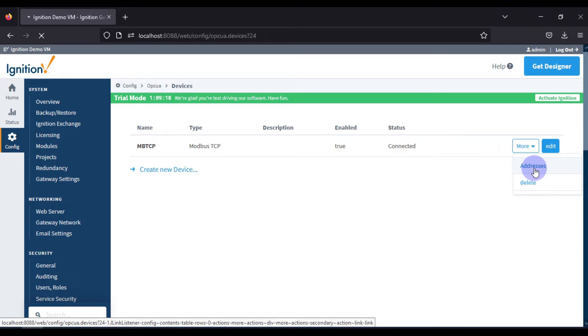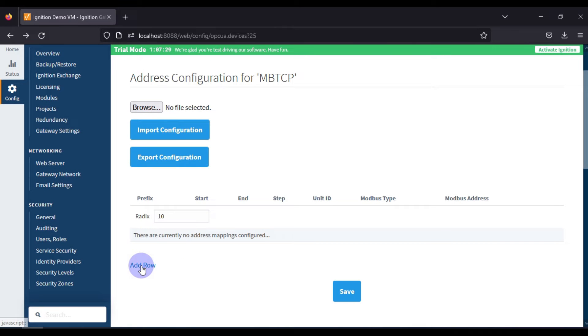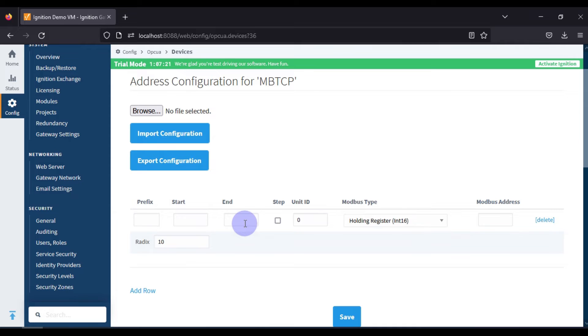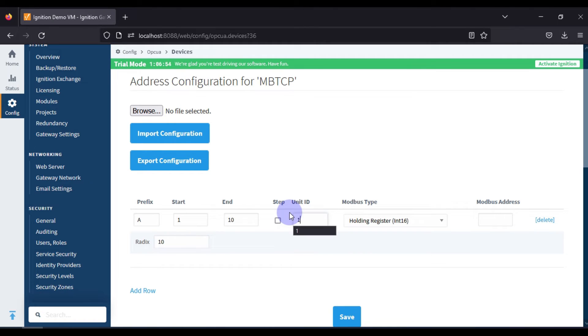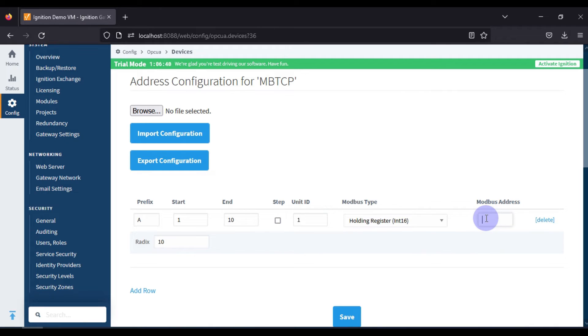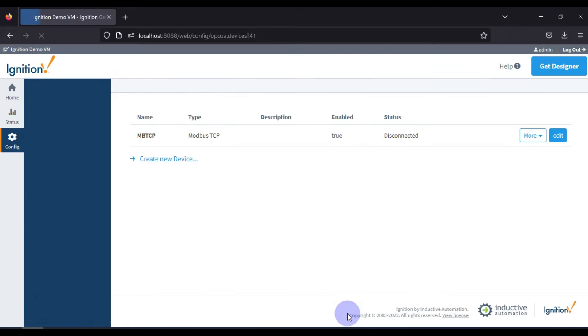Let's go back to Device Connection, open our Modbus TCP device, click More, then Addresses, and click 'Add Row'. We fill in the fields: prefix is 'A', starting address is 1, ending address is 10 — meaning we read 10 registers. The unit ID of the Modbus device is 1. We want to read a holding register in integer form, and from Modbus address 400001, so we write 1 in the address field. Then we save.